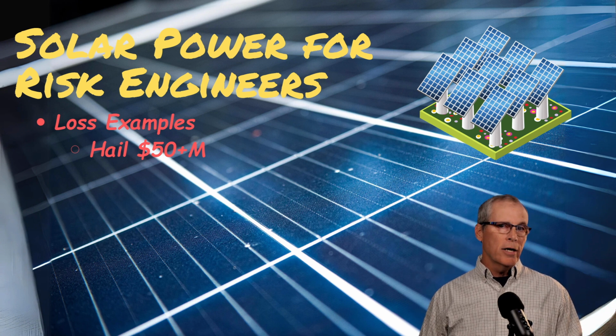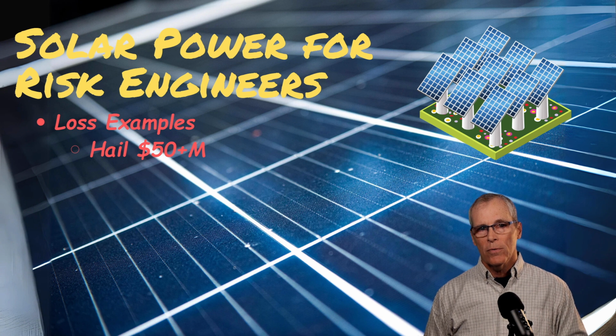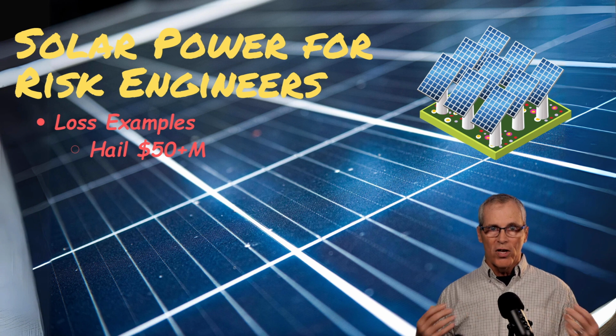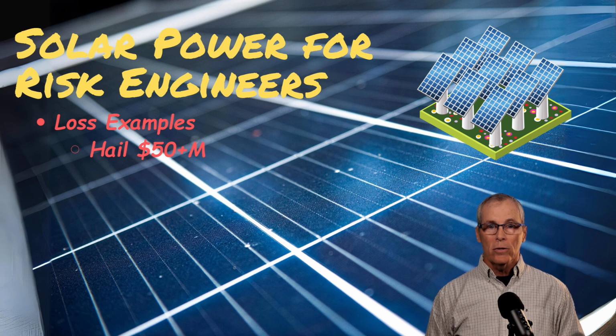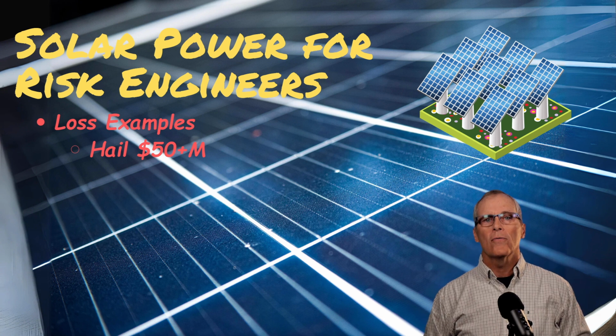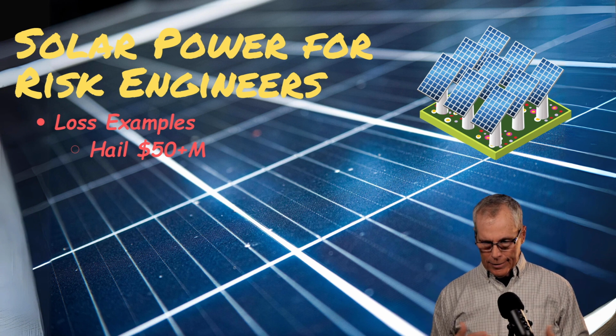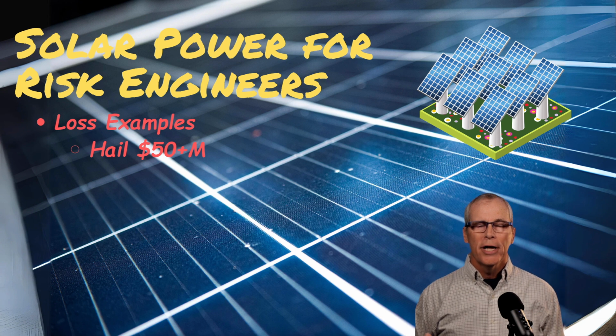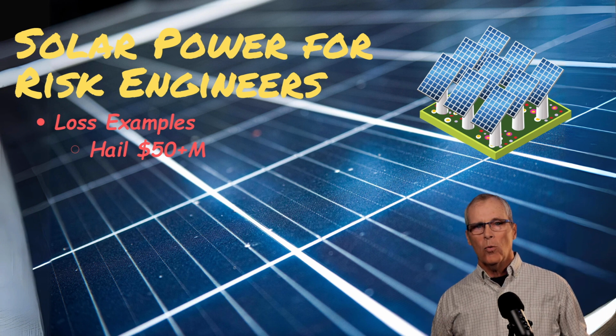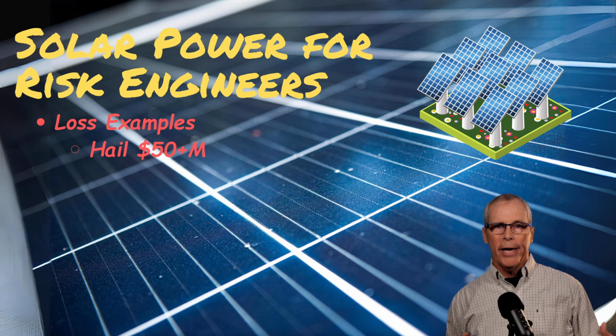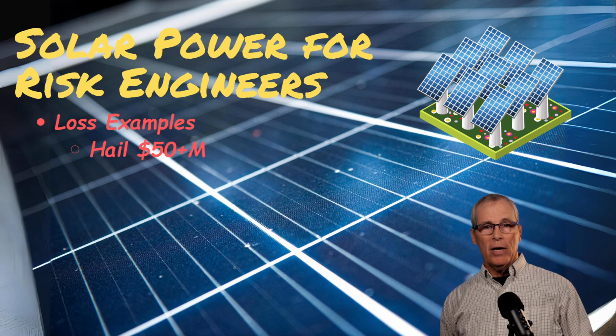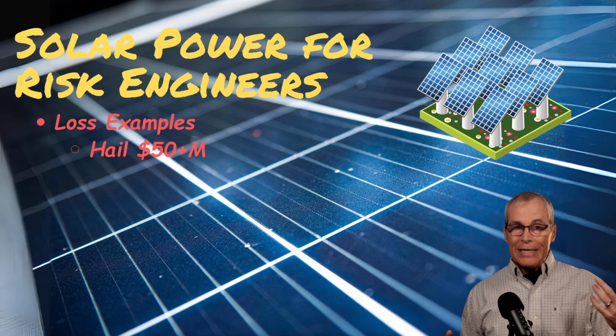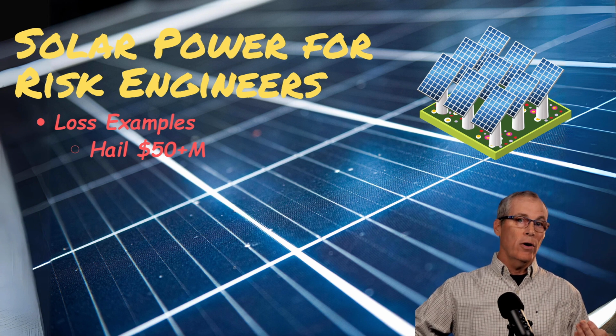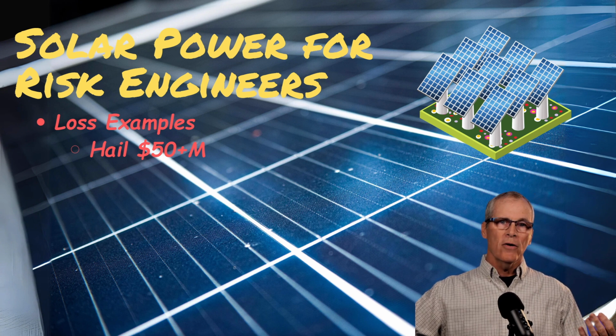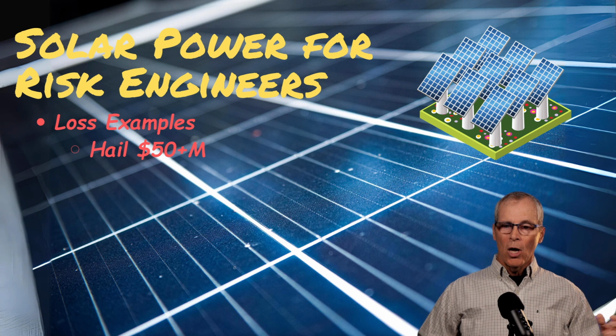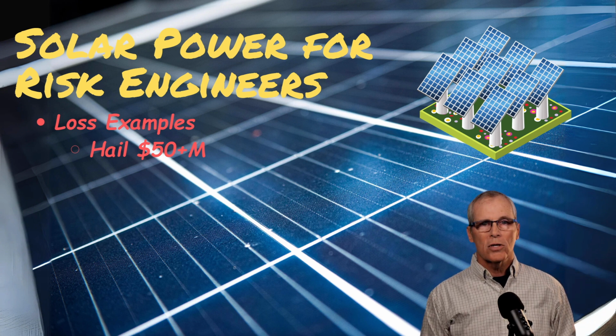There were about 800,000 panels at this solar farm, and about 300,000 of them were visibly shattered by the hail. And the hail was anywhere from 3 to 5 inches across. And again, not every panel was destroyed. So what happens when you have a string of 20 and 12 of them are destroyed and 8 of them are not? The adjuster says, we're not going to pay you for those 8. Well, we can take those 8 and 8 more from another string that aren't damaged. And if we can find enough of these non-damaged panels, we can start reconstituting the facility.